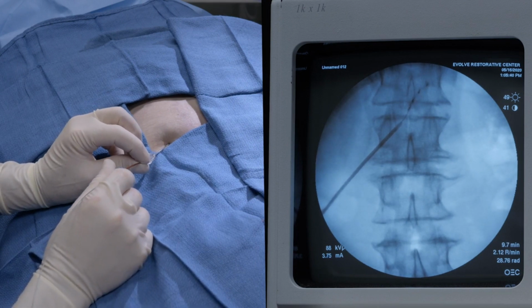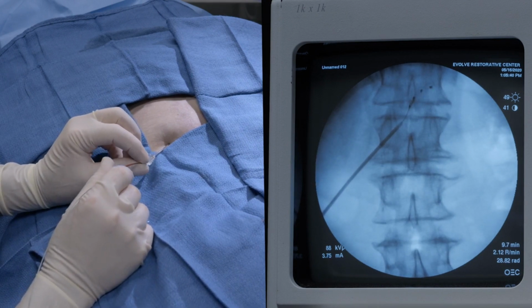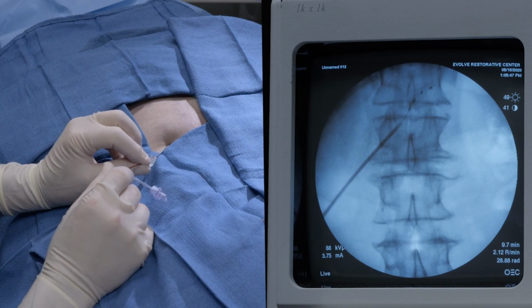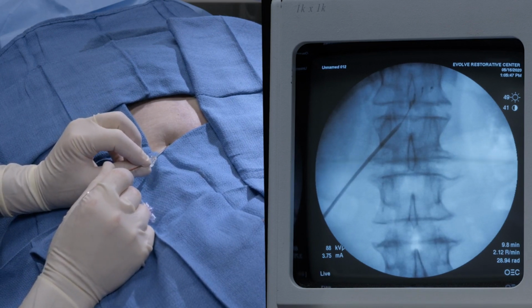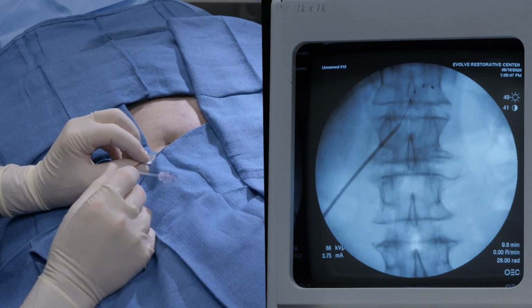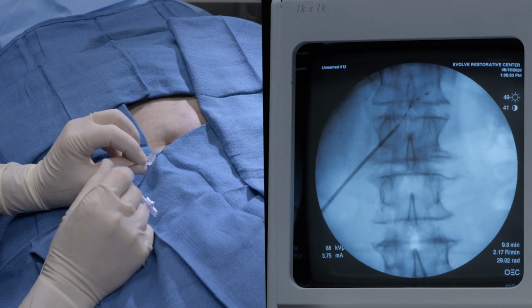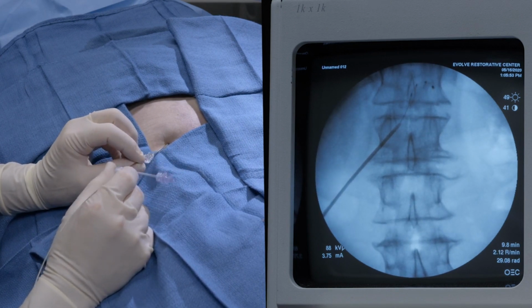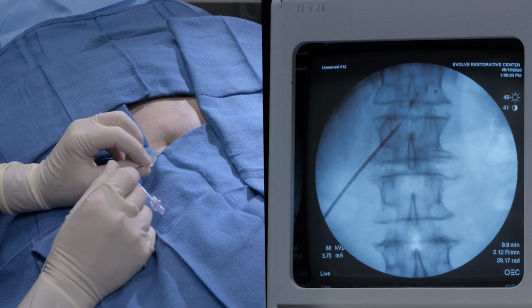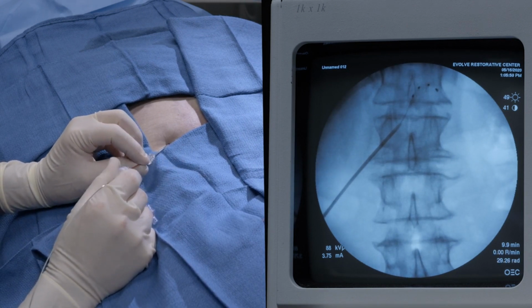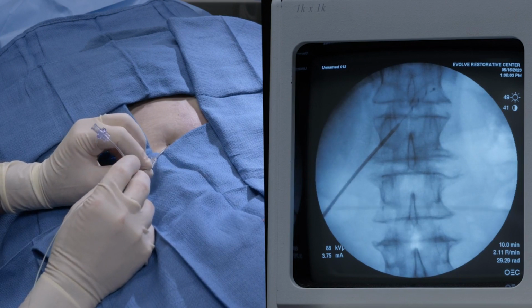So you see, as he gets close there, he's rotating it to the right, so it's going towards the pedicle. Now you're going to watch him do this, and it's not a battering ram. What he's doing is very gentle, because if you start firmly pressing that lead out, you can bend and kink the sheath. And if you kink that sheath, it's going to create a crimping on the lead, and you won't be able to deploy the lead.